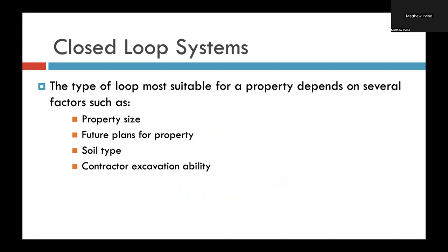The type of loop most suitable for a property depends on several factors, such as property size. The more space you have, or if you have a body of water, there's more choice to be made. Then there are future plans for the property. When you install specifically a horizontal earth loop, you're not able to build on top of it, because a horizontal earth loop at a 5 or 6 foot depth requires or relies more on direct solar radiation than a vertical loop does. So it can't be built on. You can put gardens, trees, fields, crops, anything like that is fine. Just you can't put a building over a horizontal earth loop.